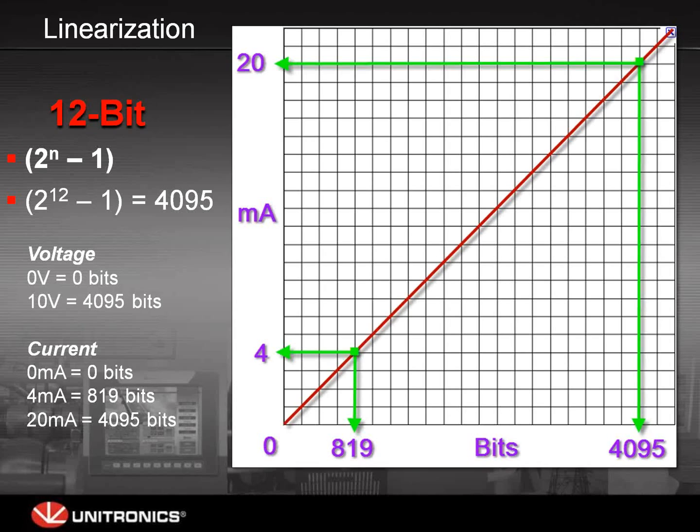As far as linearization, when you read the sensor information in, whether it's voltage or current, it's going to be converted into either a 12-bit, 14-bit, or 10-bit value. The way that you need to change those bit values into meaningful engineering units is via linearization. This graph shows how linearization actually works. In the hardware configuration, you'll define a memory integer to hold the value being read into the controller.